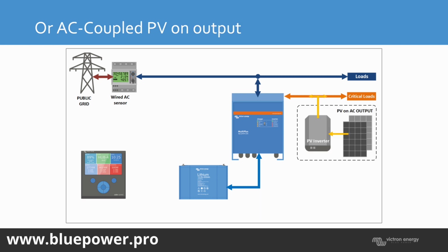Other option we've got is just an AC coupled system. These types of system are where you are going to struggle if there's an extended period of grid failure. If your battery is flat and it can't receive a charge, your inverter isn't going to switch on, and the inverter isn't going to start the Fronius inverter to start producing PV power. So in this state, you're going to have to get a generator out to site or wait for Eskom to recover the system.